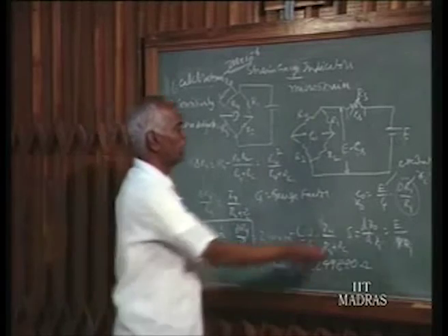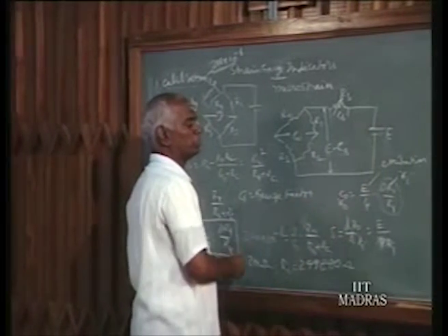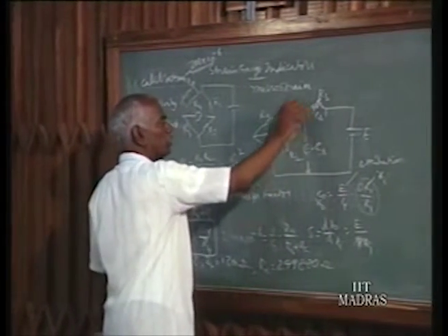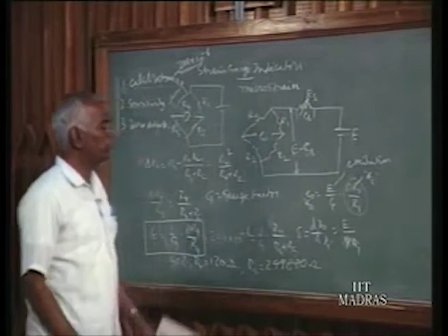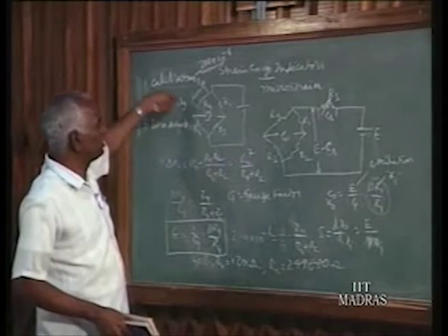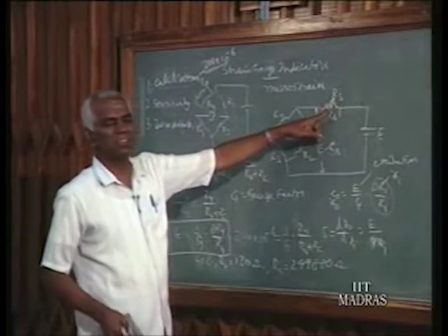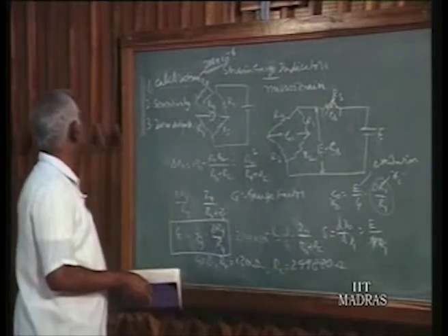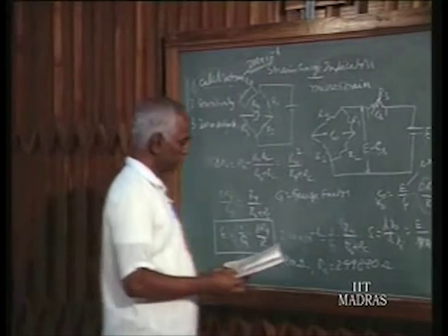Having a higher excitation value, we will have a higher output voltage. That is, output voltage is proportional to the excitation voltage. By using this property, we are changing the sensitivity. This is what we are doing. When we change the sensitivity knob, we are changing the resistance in series with the excitation. Then what is zero adjustment?